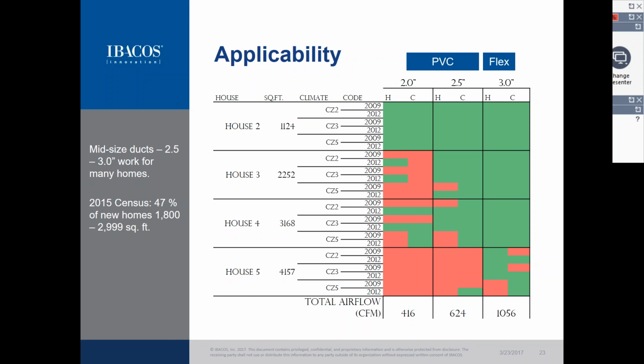So even though it's a smaller diameter, you have shorter lengths, and that helps to reduce the static pressure. And one of the benefits of the plastic materials is their smoothness. By not having those rough ridges from a flex duct, you can further reduce the static pressure requirements while maintaining the airflow. So certainly a big concern, and we recognize that for this technology to be widely adopted, there can't be a big increase in static pressure or fan energy. That's something we're trying to minimize through the design of this technology.